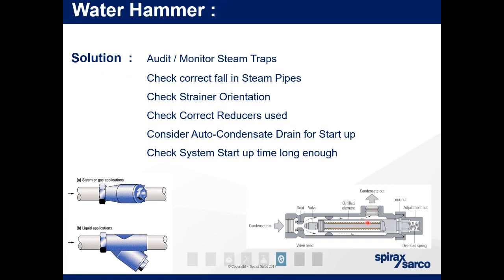By putting this device here, because this closes at 100 degrees, it uses a liquid filled capsule in here which expands and contracts. So you've got your condensate that flows in. As it starts getting to 100 degrees, to the point where it's reaching steam, this will expand and close off the drain. This is perfect for you in conjunction with those isolation valves. So you'd have the isolation valve, but it will remain open. You would put this in this orientation as well, so horizontal orientation. And you would then use this to drain the condensate from your system on startup.